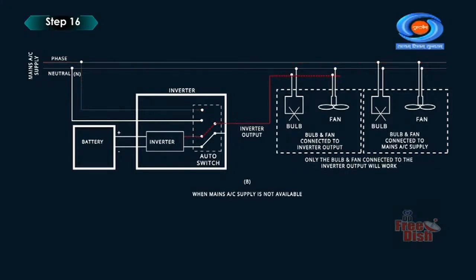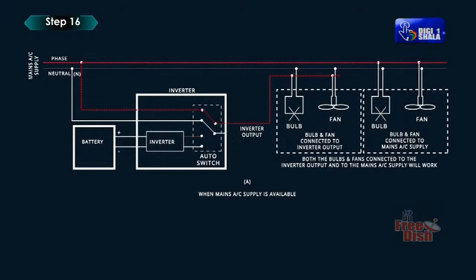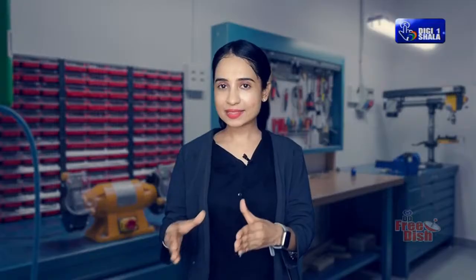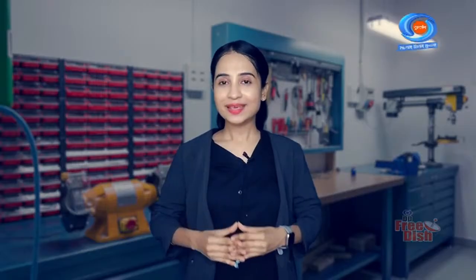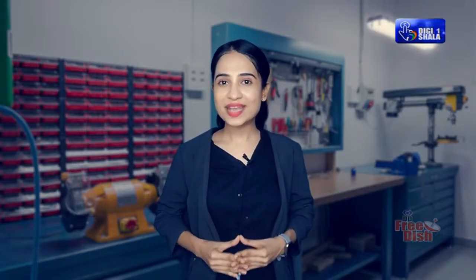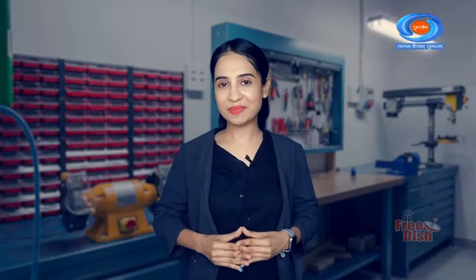During power shutdown, the devices which are directly connected to the mains AC will stop functioning, and the devices connected to the inverter will keep on working on the inverter output. When the mains AC supply returns, the inverter will again connect the load to its output. In the video, we have discussed how to select the proper rating of the inverter to install, select the capacity of the inverter and battery, calculate the battery backup time, install the inverter with battery to connect to domestic wiring, and test the inverter for its good performance on and off the supply mains.